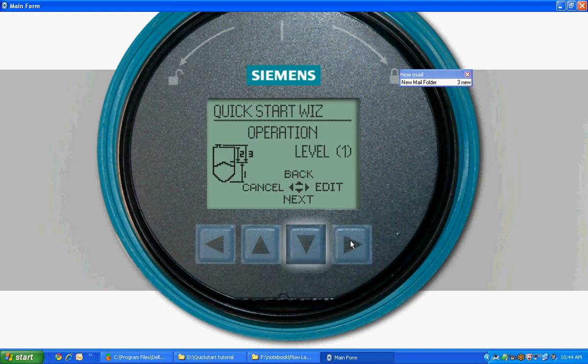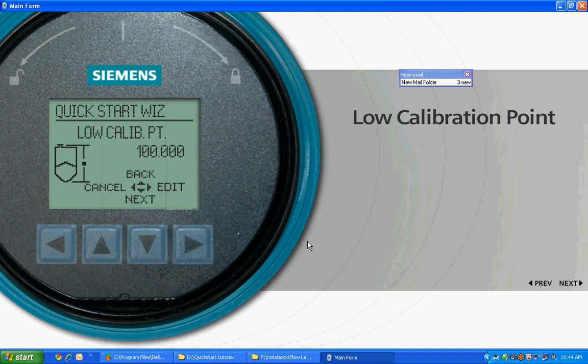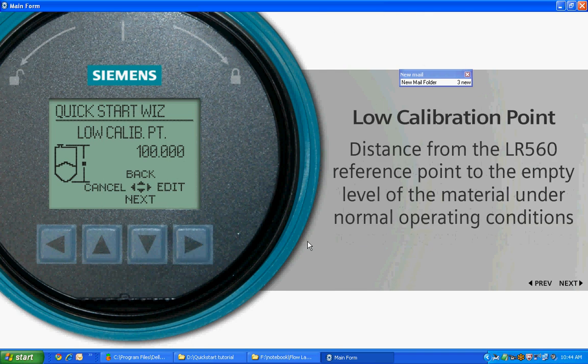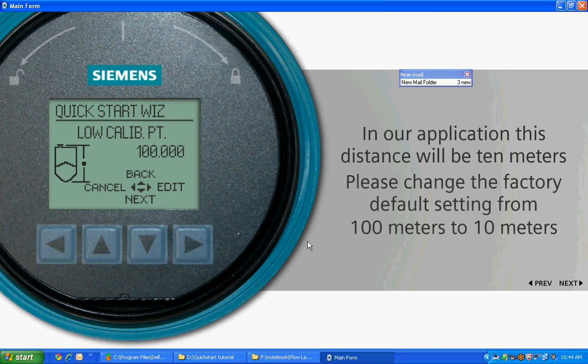Choose Next to proceed to the next parameter. The low calibration point is the distance from the LR560 reference point to the empty level of the material under normal operating conditions and represents 4 milliamps for a 4 to 20 milliamp device. In our application, this distance will be 10 meters. Please change the default factory setting from 100 meters to 10 meters.